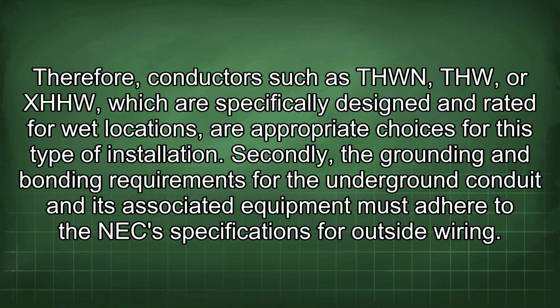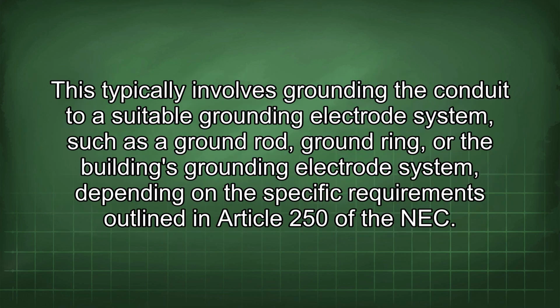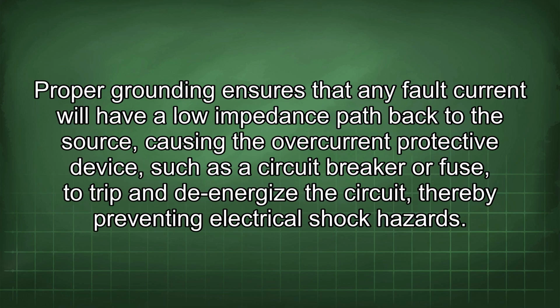Secondly, the grounding and bonding requirements for the underground conduit and its associated equipment must adhere to the NEC specifications for outside wiring. This typically involves grounding the conduit to a suitable grounding electrode system such as a ground rod, ground ring, or the building's grounding electrode system, depending on the specific requirements outlined in Article 250 of the NEC. Proper grounding ensures that any fault current will have a low impedance path back to the source, causing the overcurrent protective device, such as a circuit breaker or fuse, to trip and de-energize the circuit, thereby preventing electrical shock hazards.